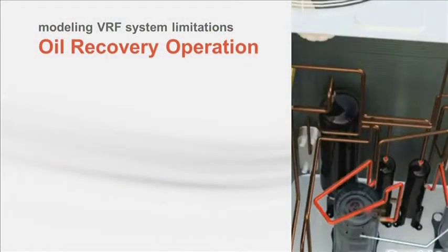Remember the oil recovery or flush cycle that Paul talked about earlier? Any oil that has made it past the oil separator must be periodically recovered. During the oil recovery operation, the system's ability to provide conditioned air is limited, which will affect the space temperature and load. This is something that is difficult for simulation programs to estimate because the operations are unique to system manufacturers and oil recovery cycle durations vary.